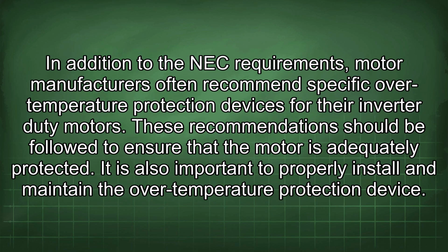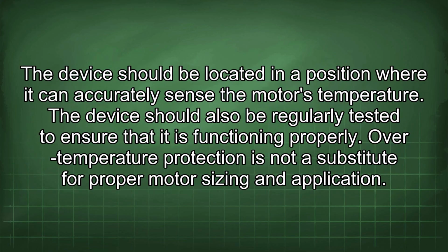In addition to the NEC requirements, motor manufacturers often recommend specific over-temperature protection devices for their inverter duty motors. These recommendations should be followed to ensure that the motor is adequately protected. It is also important to properly install and maintain the over-temperature protection device. The device should be located in a position where it can accurately sense the motor's temperature. The device should also be regularly tested to ensure that it is functioning properly.